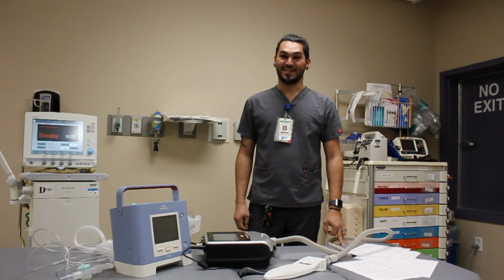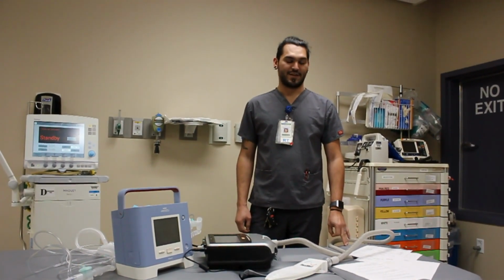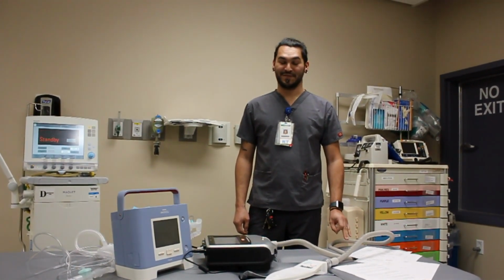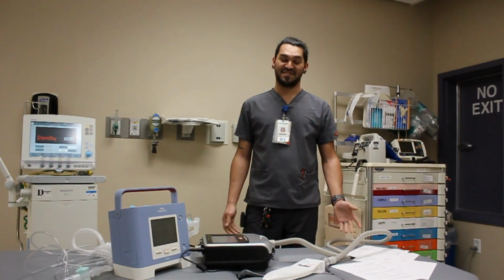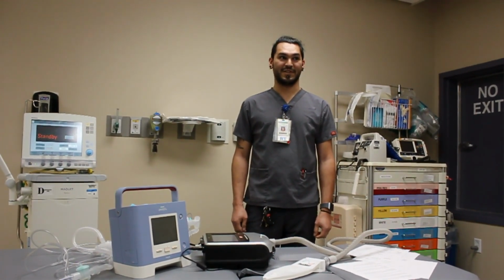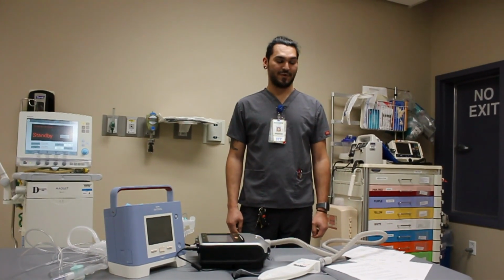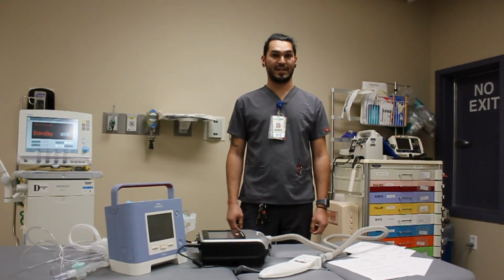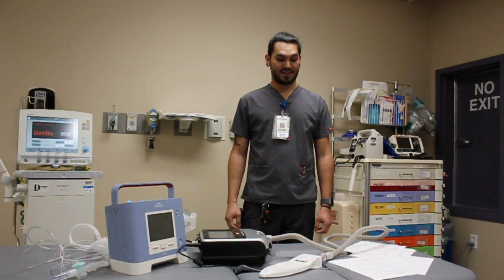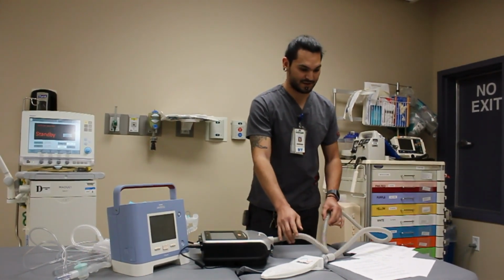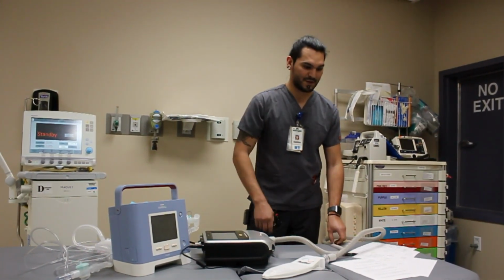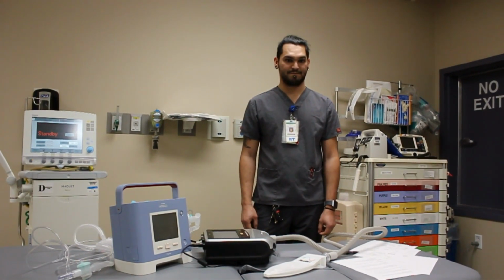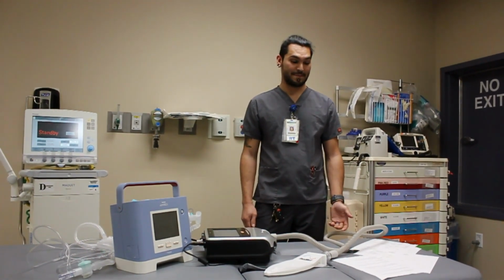Next alarm we're going to go over is high respiratory rate. We would look and find out, is your patient anxious? Are they worked up? Are they fussy? Are we having increased work of breathing because we're in any kind of distress? Is there water sloshing inside the tubing that's causing a double trigger? Or is their trigger sensitivity too high?